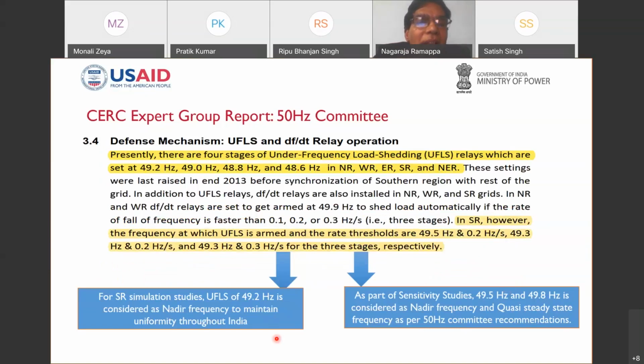Therefore, if you look at the CERC expert group, there is one more thing they are talking about, the under frequency load shedding. See, very important, when a fault occurs in the system, whenever a major disturbance occurs, the frequency will vary, basically because of the electrical power and the mechanical power.